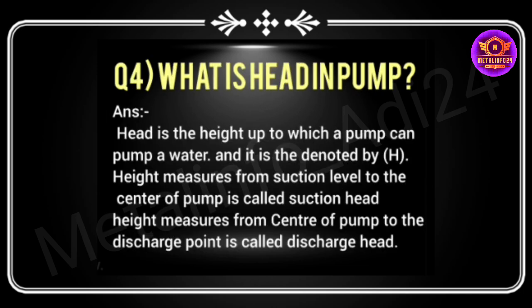4 number, what is head in pump? Head is the height up to which a pump can pump a water and it is denoted by h. Height measured from suction level to the center of pump is called suction head. Height measured from center of pump to the discharge point is called discharge head.